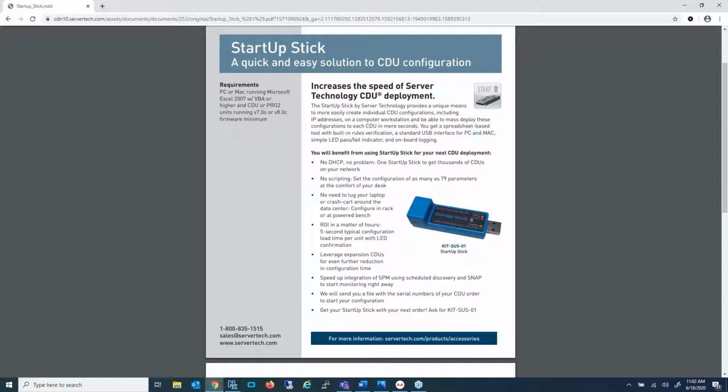With PDUs already installed in the rack or cabinet and energized for at least 3 minutes, each PDU can be configured in about 5 to 6 seconds. So if the PDUs are all lined up in a row at the same facility, you configure about 15 seconds per PDU as you move down the line.